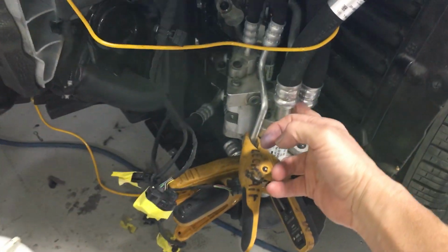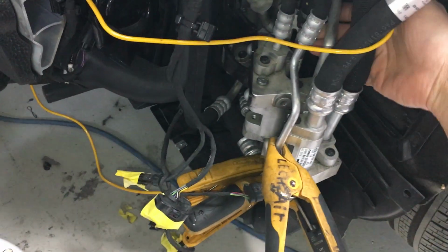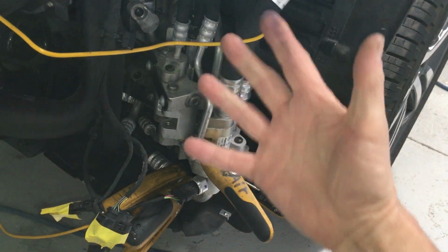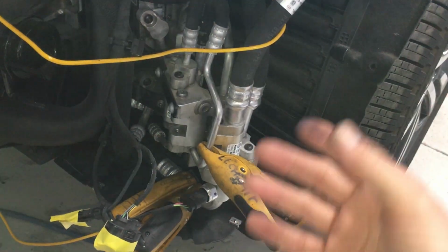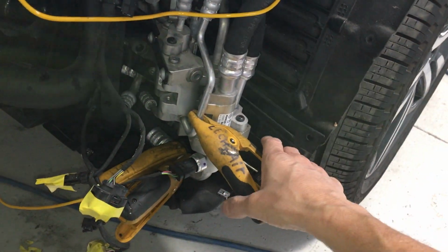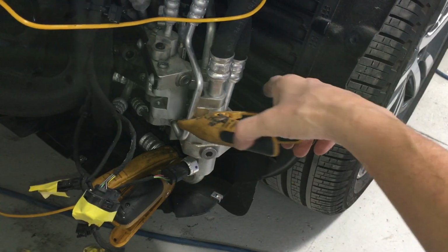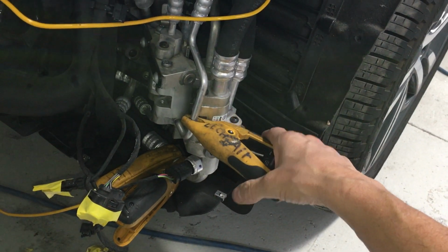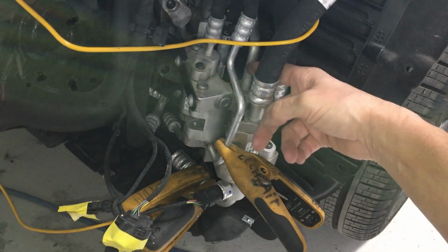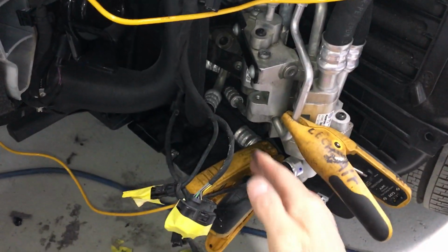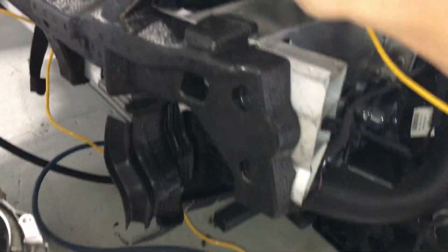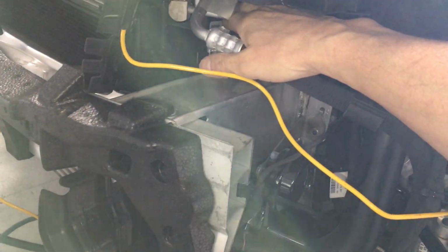So what I was trying to do, I'm going to try to trace out what line turns. This is going to take a lot of time, and I actually don't have the time. So what I need to do, if you don't have a book and you have one of these systems, and this is what I'm going to have to start doing, is get your data log gauges, get your clamp-ons, and start moving them around. You can use your finger, but if you want to get accurate readings, you have to figure out where.